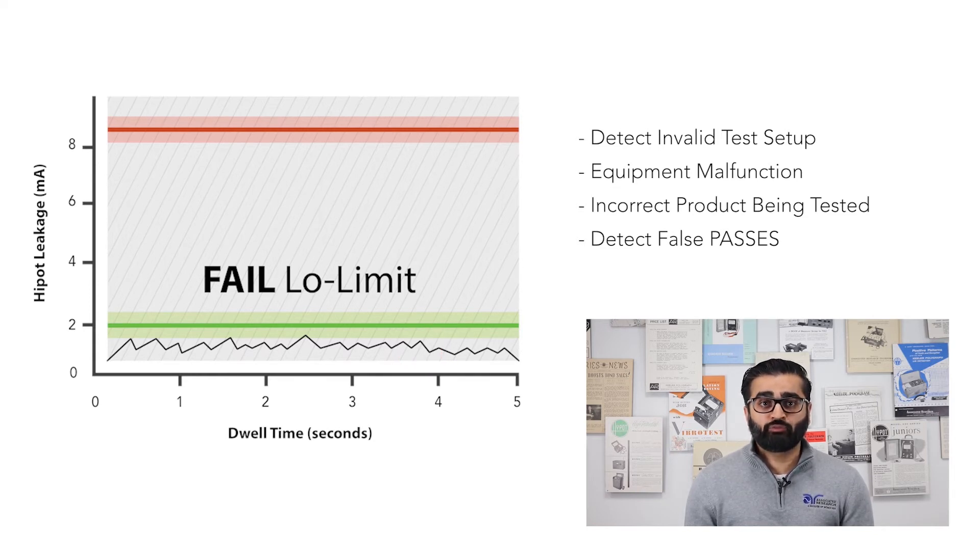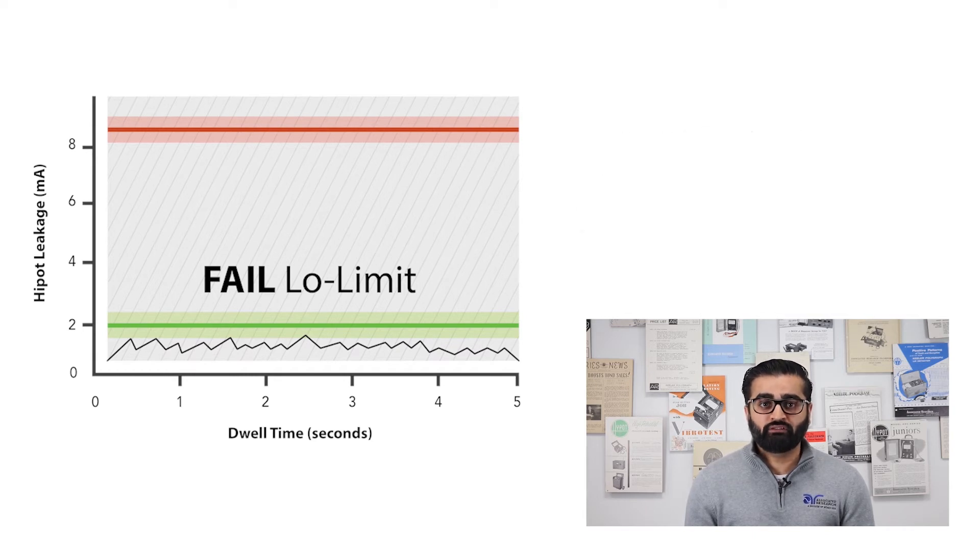Setting the low limit indicates that you expect a certain amount of leakage current for a device on the test. At the minimum, the leakage current should exceed this low limit value in order to be considered a valid test.